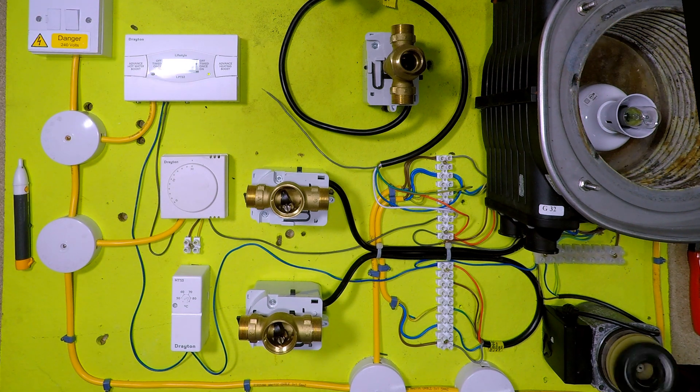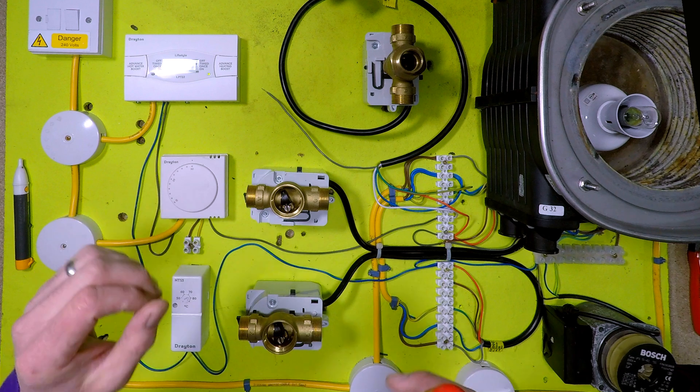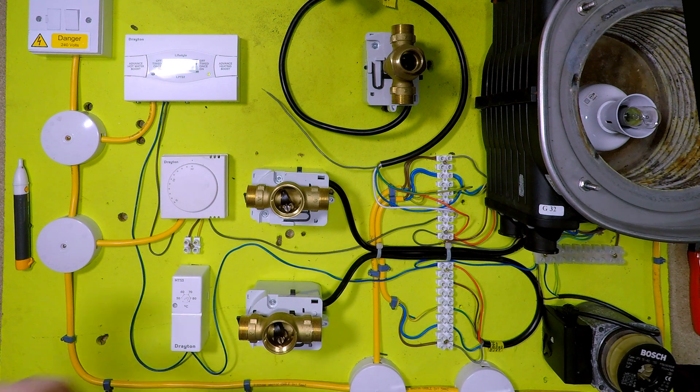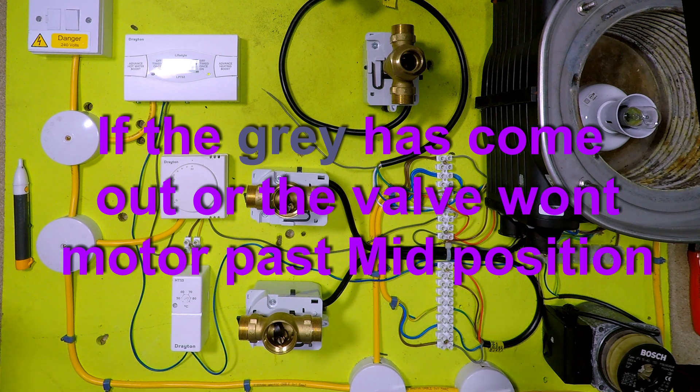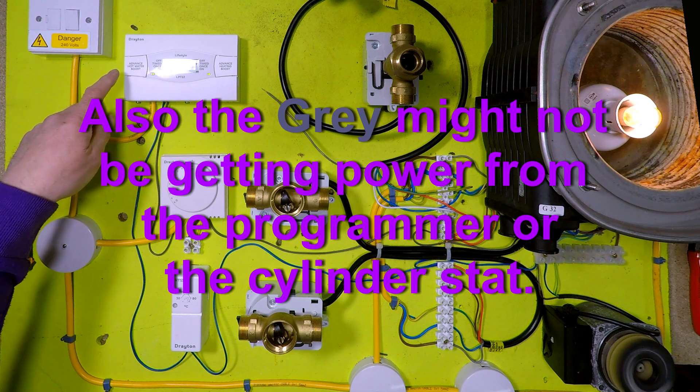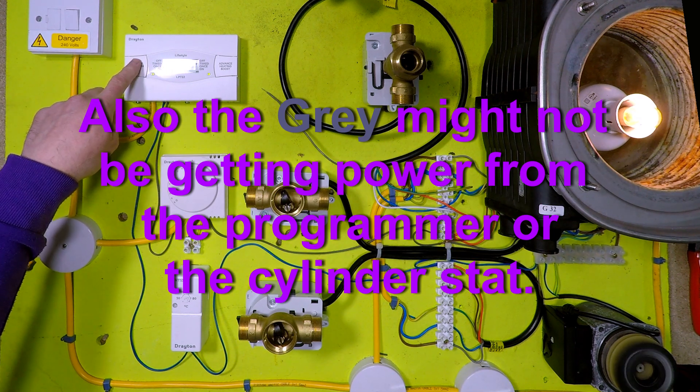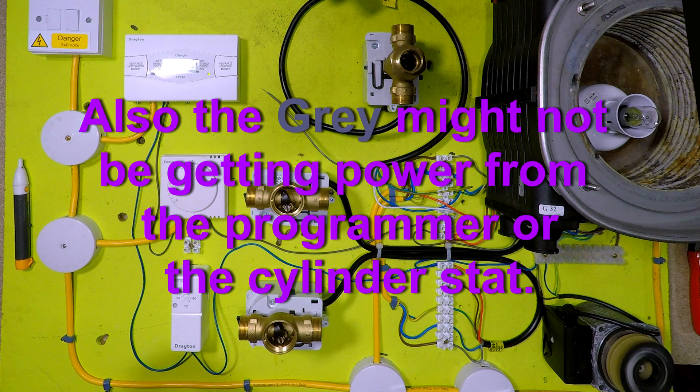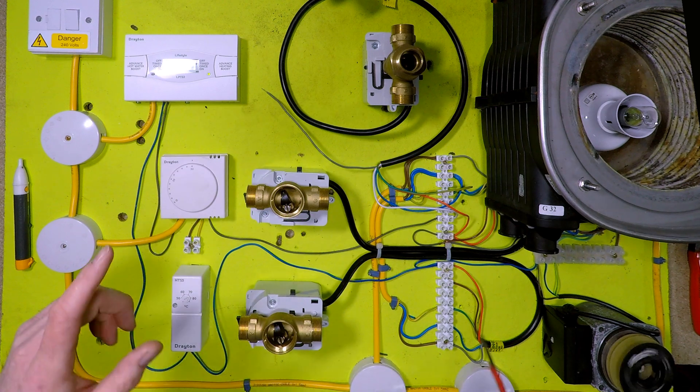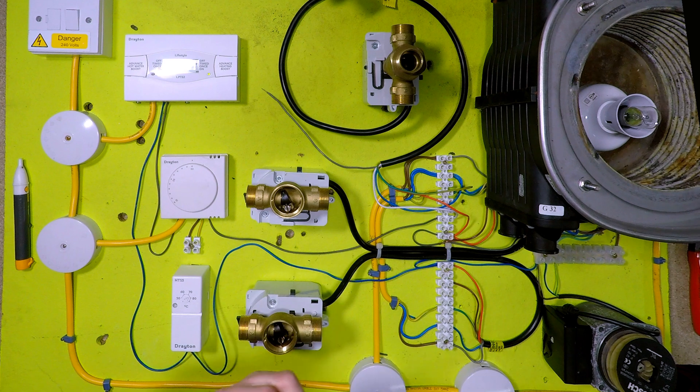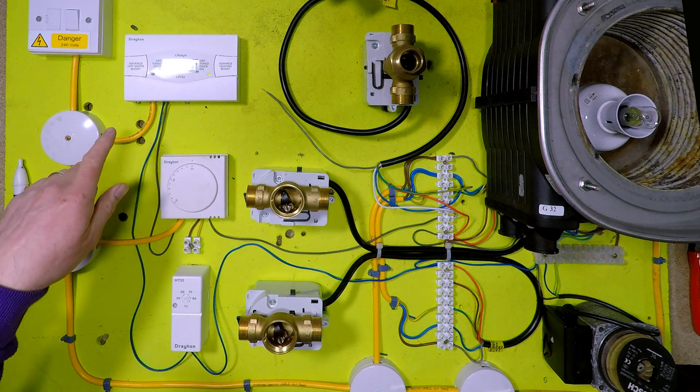So the fault situation you get here is people will say my heating only works for 10 minutes or let's say for half an hour a day, because your heating will only work when the hot water is being heated. All right, so you can see how in this situation here you could never have heating only. It wouldn't work.